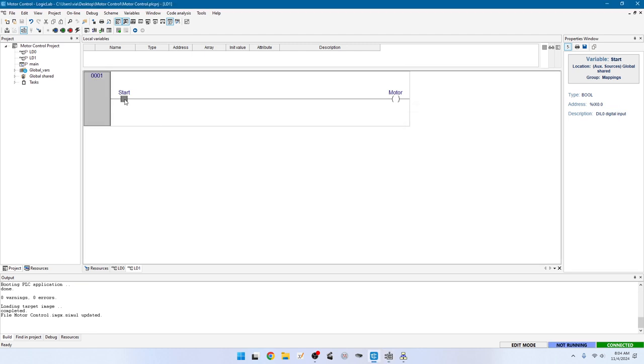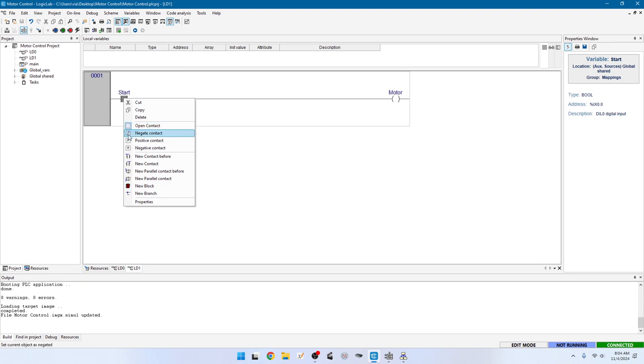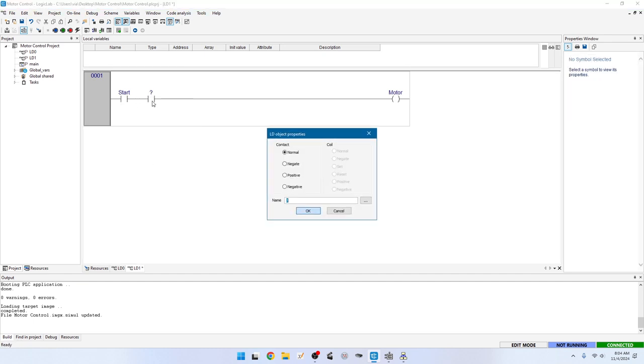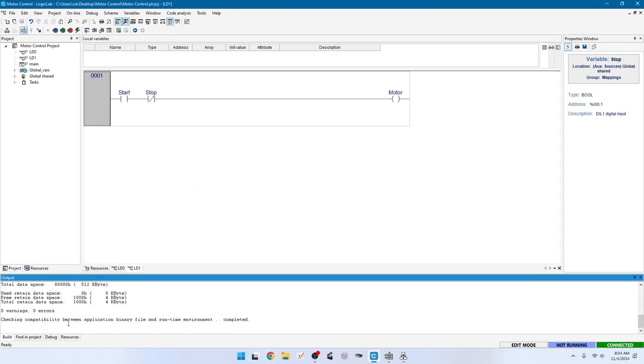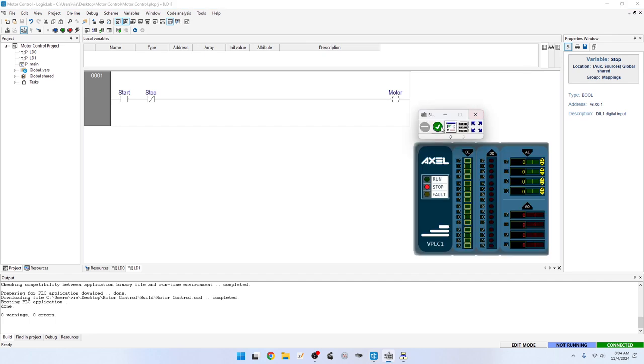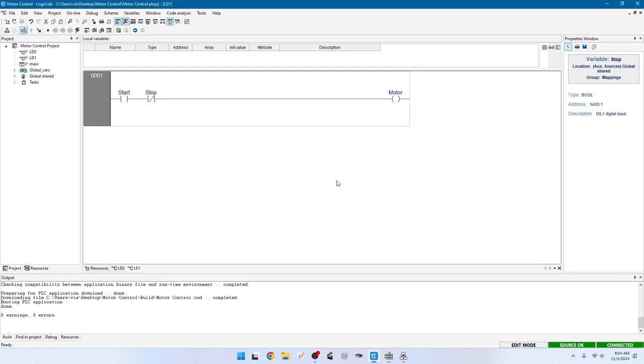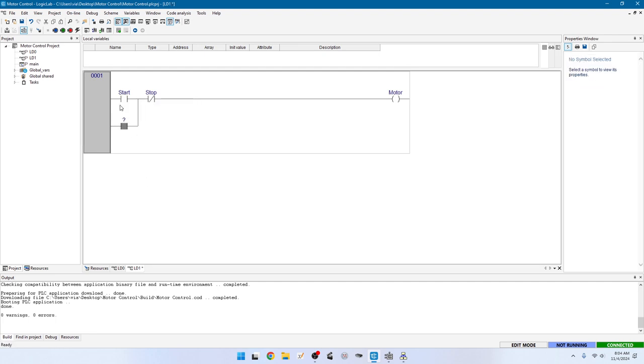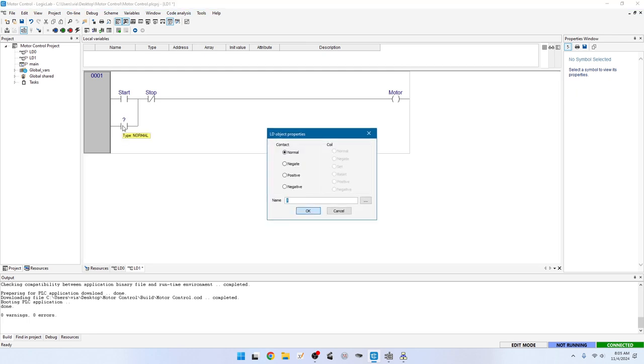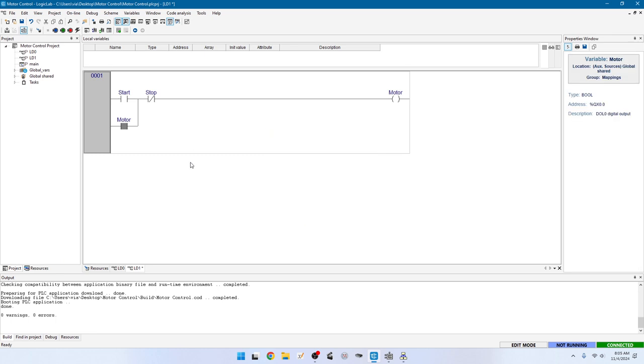Go back and select the start contact, right-click, and put a new contact after that. Double-click on it and make this the stop button with a negated contact — a normally closed contact. F7, F5, start running. When we press start and then press stop, it opens the connection and turns everything off. Now let's select start and make a new parallel contact — an OR operation, with two contacts in parallel. Then this is an AND operation. Double-click and make this the motor signal. This is a latching operation.